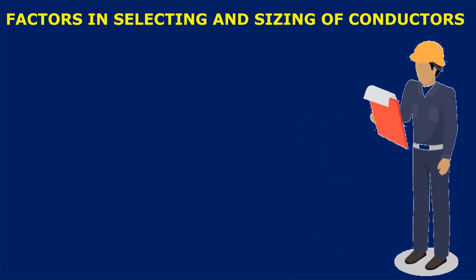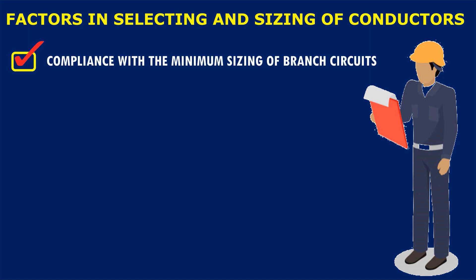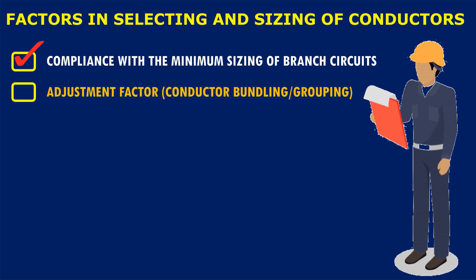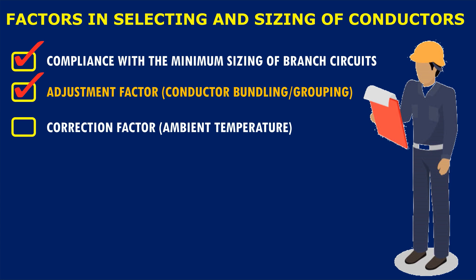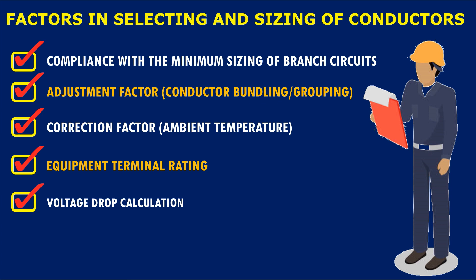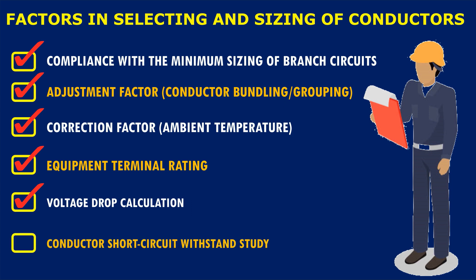We now understand all the factors to consider in choosing the correct size of conductors. These are: compliance with minimum sizing of branch circuits and feeders; correction and adjustment factors that reduce the conductor's ampacities; conductor temperature rating determined by the connected equipment terminal with the lowest temperature rating; voltage drop, which should be within accepted limits to improve performance and efficiency; and the conductor's ability to withstand short circuit current without thermal damage until the overcurrent protective device trips or clears the fault. Hence, selecting the correct size of conductors involves referencing more than one section and chapter in the Philippine Electrical Code.